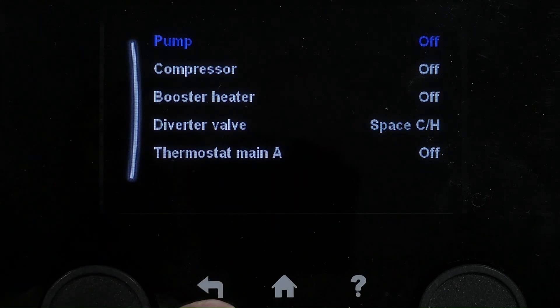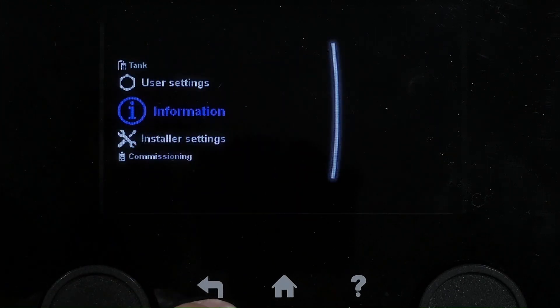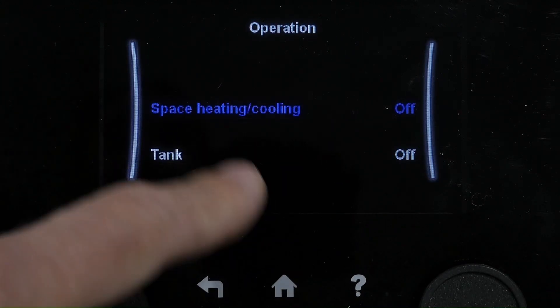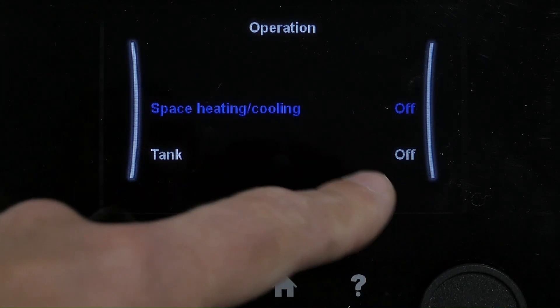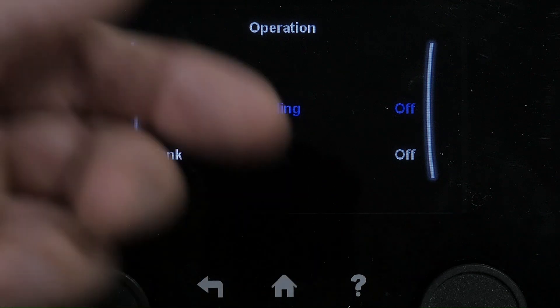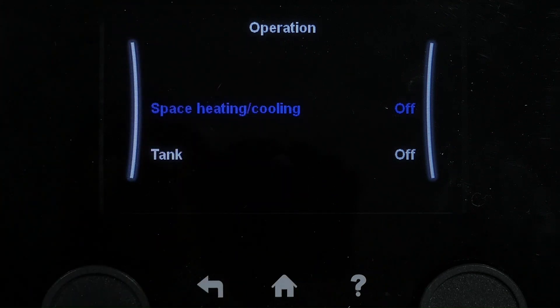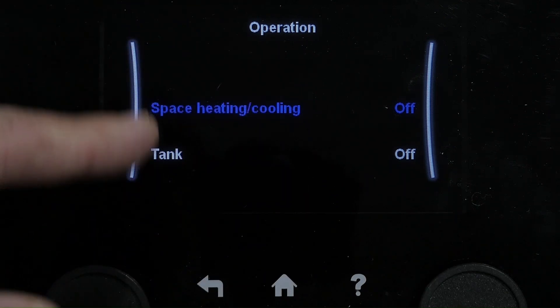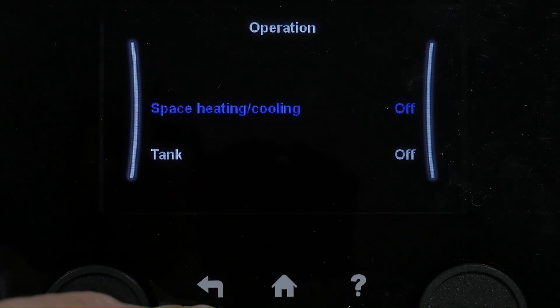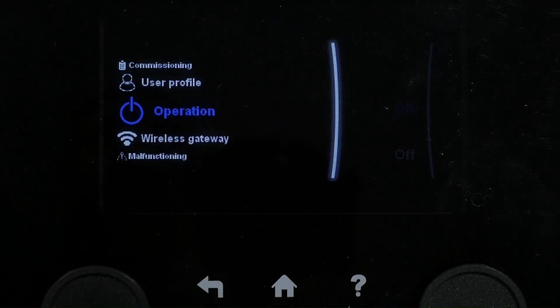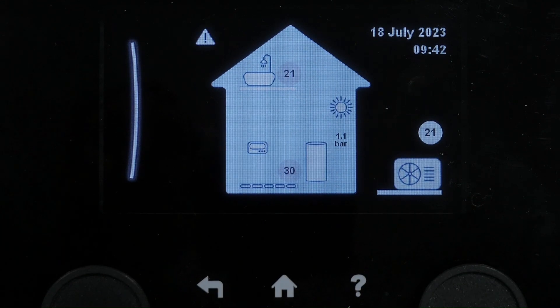It's important to make sure the operation modes are running — you can see at the moment they're off. So even if we did have a room thermostat demand, nothing would be happening. It's important to remember that these operation modes need to be on as well, and that will help you determine what's happening with the heat pump.